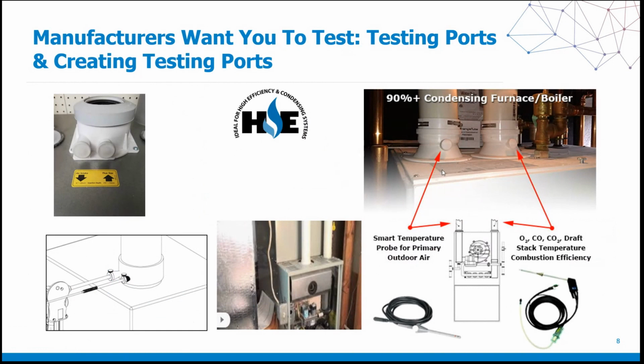Manufacturers want you to test. They are creating testing ports. Here and here, as you see, these are not base and treble knobs, everyone. These are testing ports for you to properly do a combustion test. Also here on this concentric package, you see the exact same ports here as well. And down here, you don't see any testing ports on this high efficiency furnace. However, if you don't see them, guess what? You can make them. All you need to do is just drill a little hole in these intake and exhaust pipes here, and then insert a tap screw when you're done, but you create your own test port to be able to do a combustion analysis.